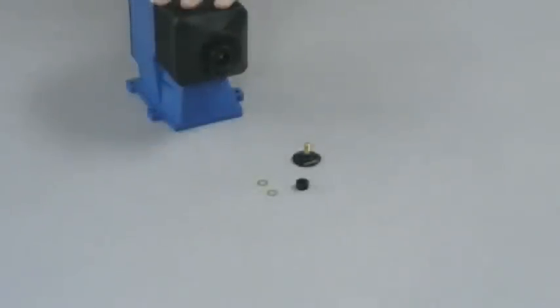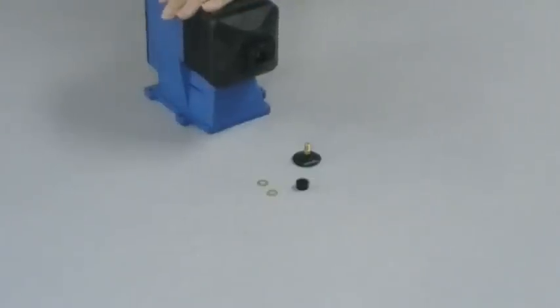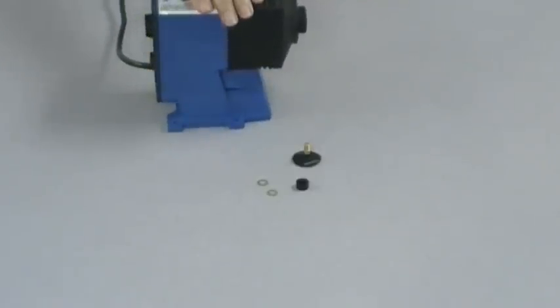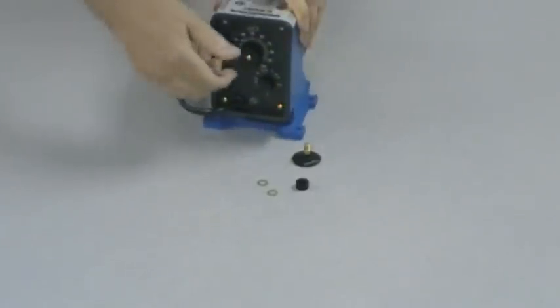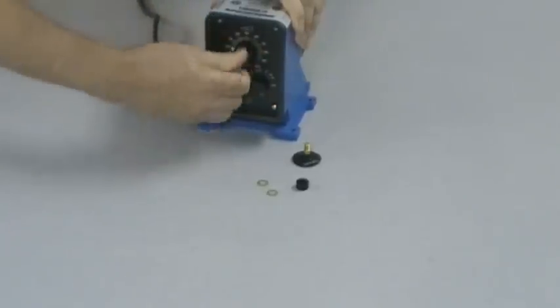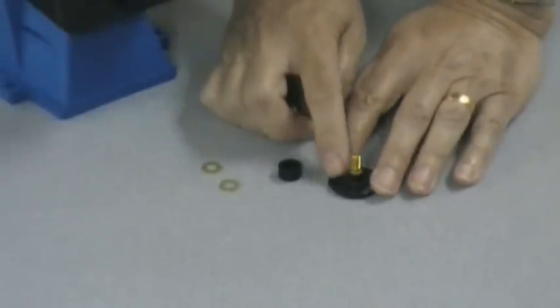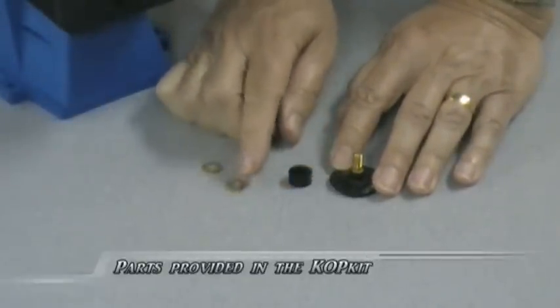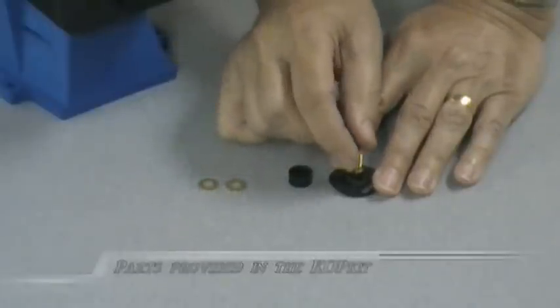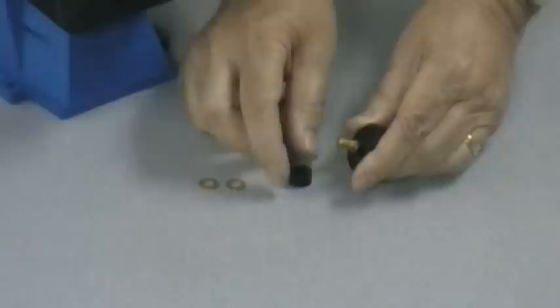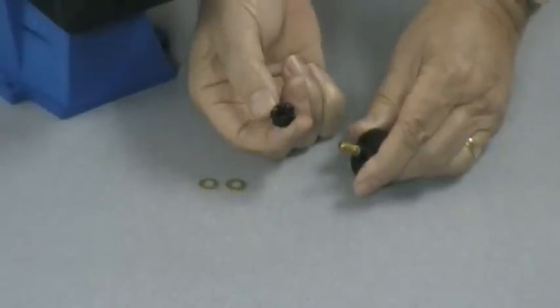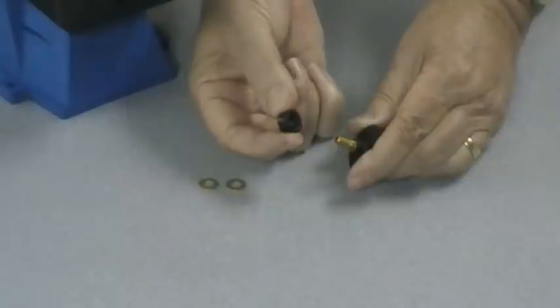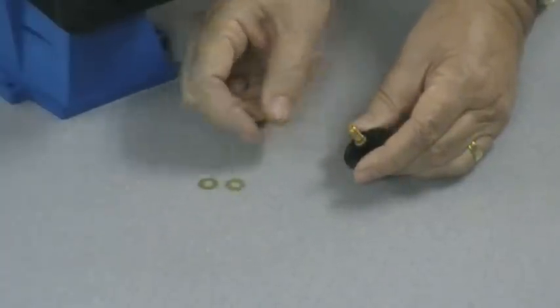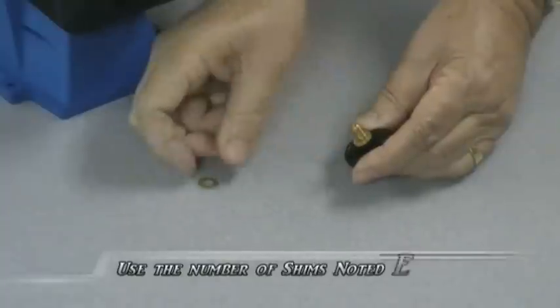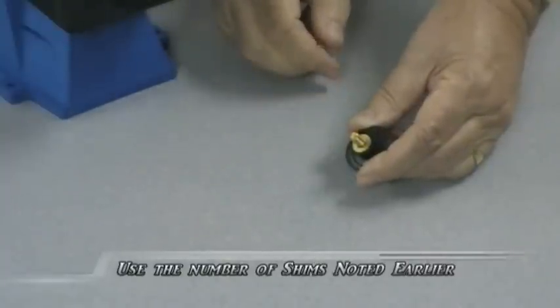Next, we want to reinstall the new diaphragm. To do that, we need to plug the pump in, adjust the stroke length to 50%. The new diaphragm is installed using the diaphragm, the deflection plate, and the 2 brass shims. First, we need a silicone-based lubricant to lubricate the parts. The deflection plate has a radius on one side. That radius goes against the diaphragm, and the brass shims then go behind the deflection plate.